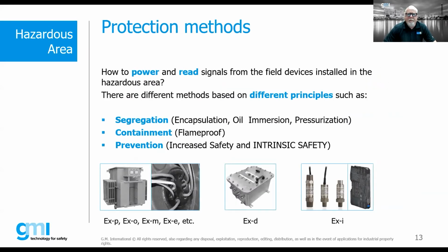So, protection methods. Some of the really common protection methods in the hazardous location world are things like segregation, where we're encapsulating something. We may be oil immersing. Pressurization, a pressurized panel, is a good example of segregation, where we're segregating the flammable gas-air mixture from the source of ignition in some way, shape, or form. Containment, a very common practice, is represented by flameproof. Flameproof assumes that we're going to have all three legs of that triangle, if you will, in sufficient quantity with sufficient energy. We're going to contain the explosion on the inside of a piece of equipment that's deemed flameproof.